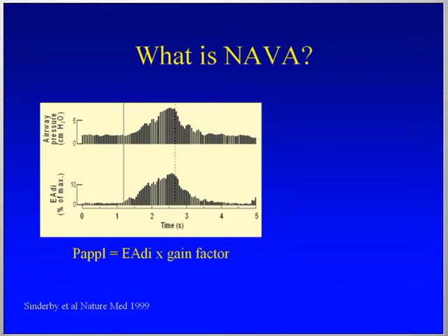This is neurally adjusted ventilation. It is a partial ventilatory assist mode, where the airway pressure is delivered in proportion to the electrical activity of the diaphragm. So this is one inspiration here. With the prototype of NAVA that we're using today, we are triggering the assist when the diaphragm electrical activity begins to increase. We are delivering the assist proportionally and instantaneously every 16 milliseconds until the diaphragm electrical activity begins to go down, and then we are cycling off the assist.